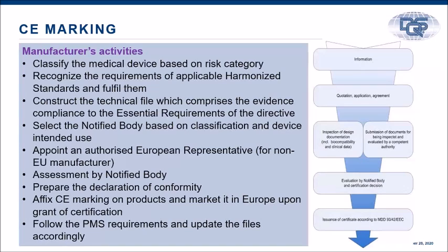In the European Union under MDD, they had a list of standards called harmonized standards, which are voluntary in nature, and that is given a status that gives presumption of conformity to the essential requirements which were there as a part of the medical device directive. Similarly, though there is no published harmonized standard list under MDR, we hope that it will be out soon.